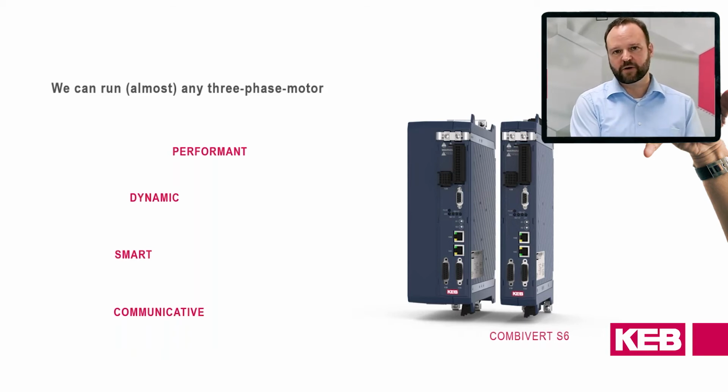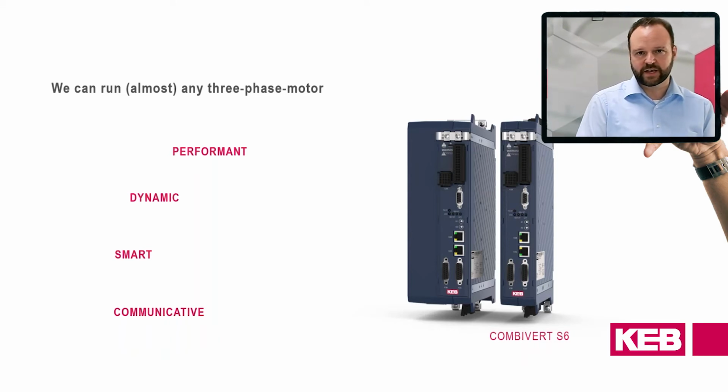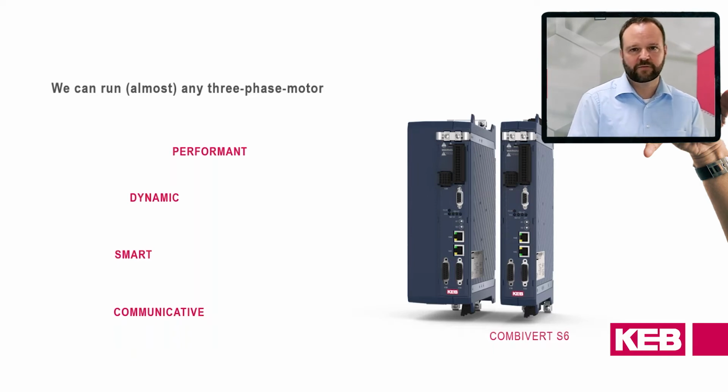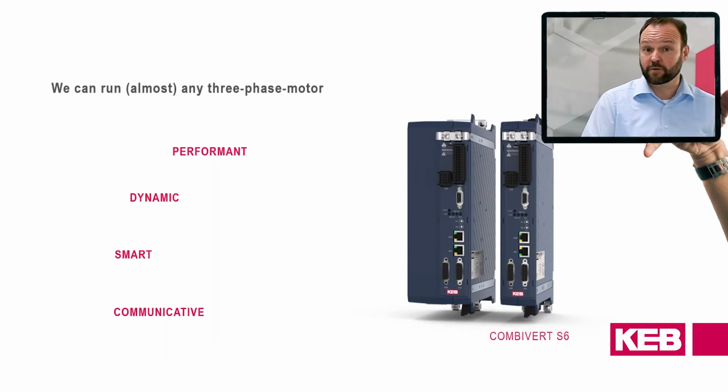So now we have talked about the motor side, but on the other hand, we have the control side, of course. Also there, we support different kinds of fieldbus systems like EtherCAT, Profinet, EtherNet/IP, Modbus TCP, POWERLINK, VARAN, CAN, and you can also change this by parameter for some of these bus systems. So this makes it usable for a wide range of controllers, and it makes it very flexible in the range of applications you can use this drive on.